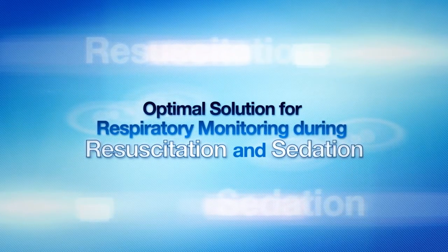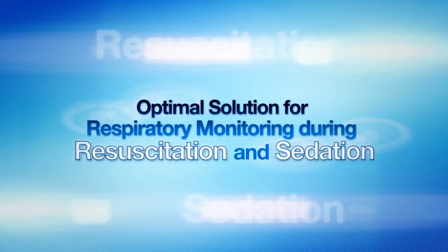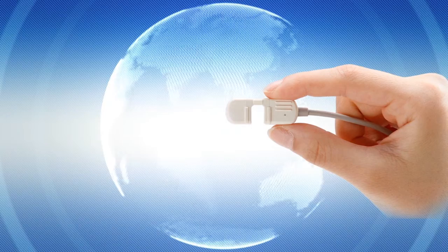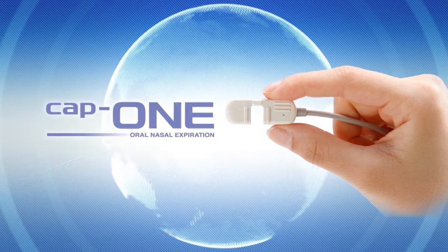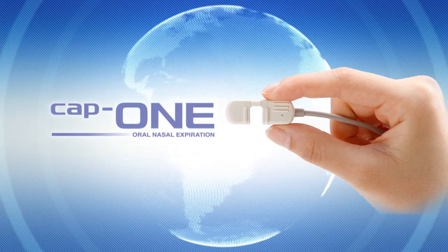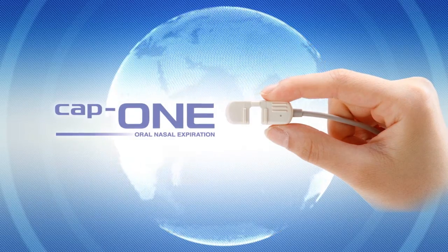Nihon Kohden offers an optimal solution for respiratory monitoring during resuscitation and sedation. Reliable monitoring of ventilatory status can be achieved with cap-ONE capnography technology, the world's first mainstream CO2 sensor, which is specifically designed for both intubated and non-intubated patients.